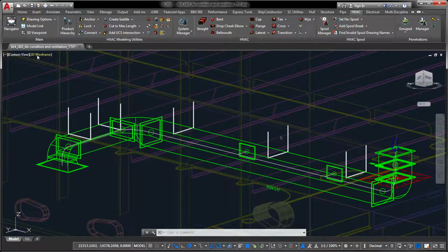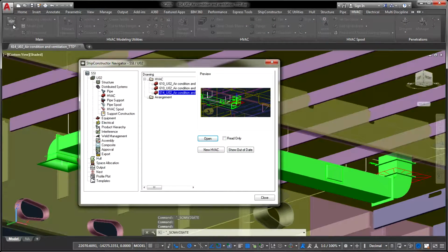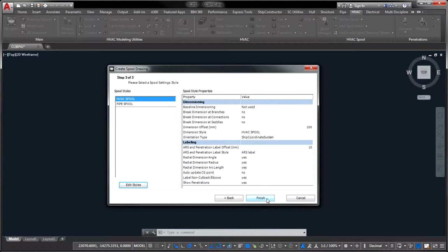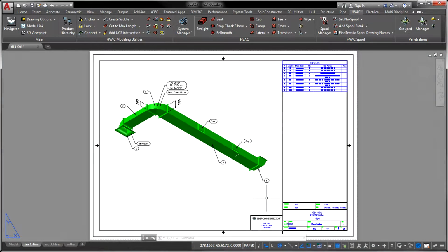Additionally, the drop cheek elbow allows for a transition in its profile width as well as a slant in its cheeks. When setting a cheek at an angle, an offset parameter can be adjusted for the in and out ends of the elbow so that only one of the sides is dropped while the other one is kept flush.